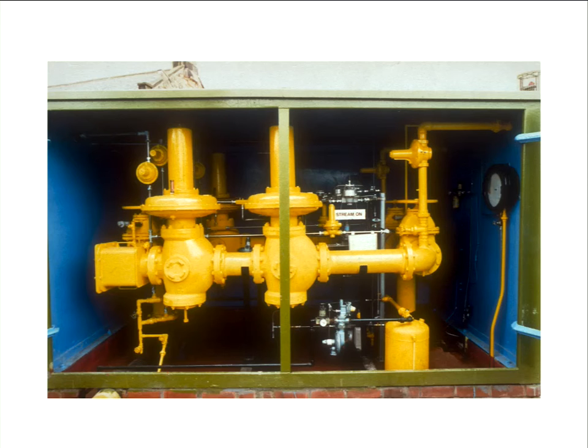But this has been designed. So the pipeline's designed, and then your pressure installation is designed to limit the possibility of that running above 38 bar. But this one's quite a managed system, so I'll talk about SCADA systems and so on, so control rooms and monitoring. But the vast majority of these installations probably have no remote monitoring, so it just sits on a fixed pressure all the time.